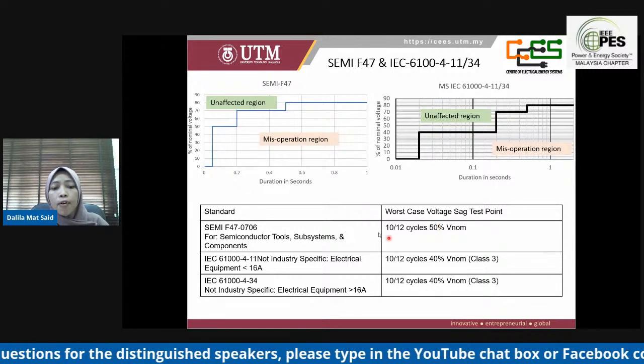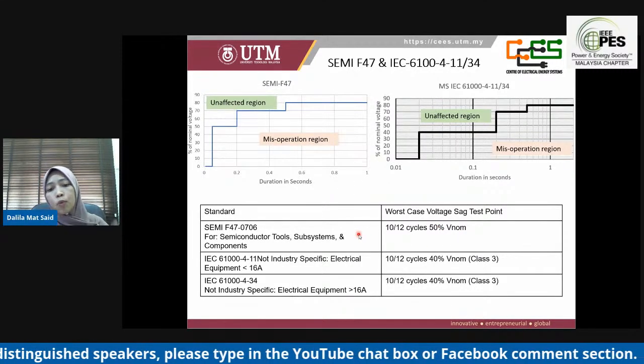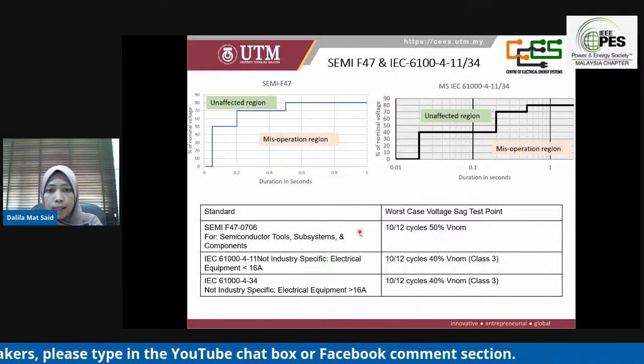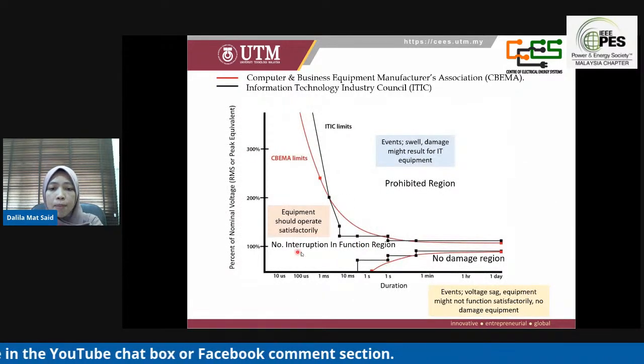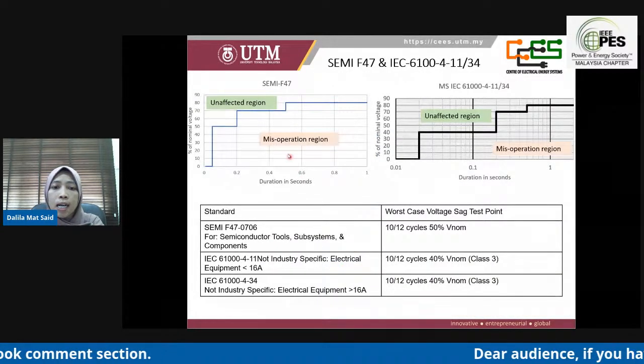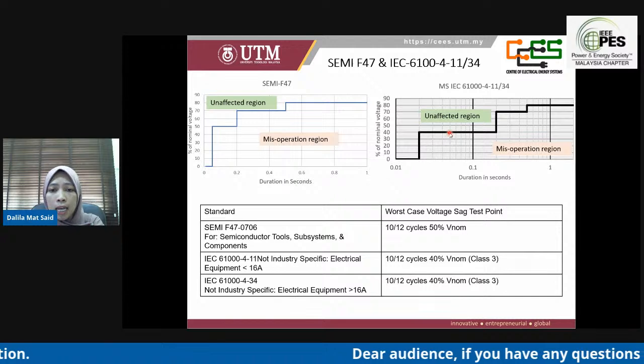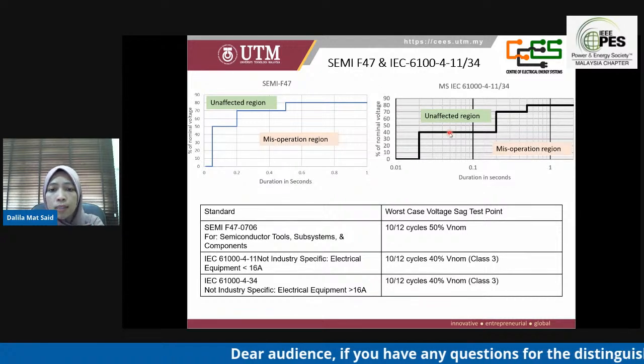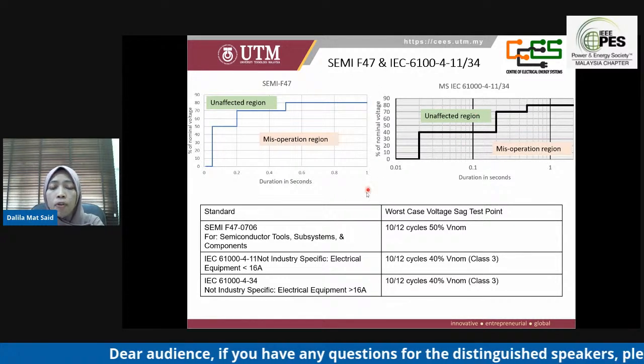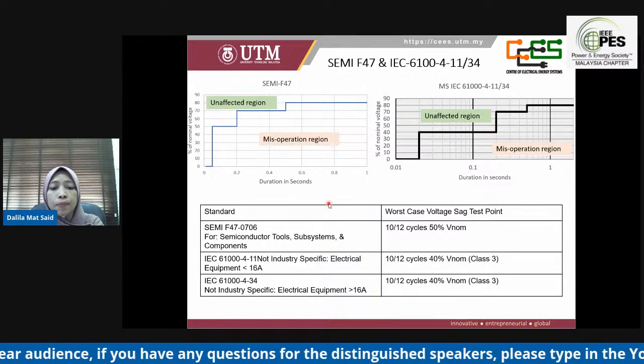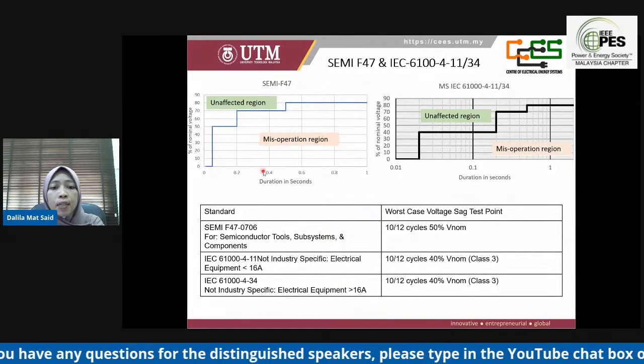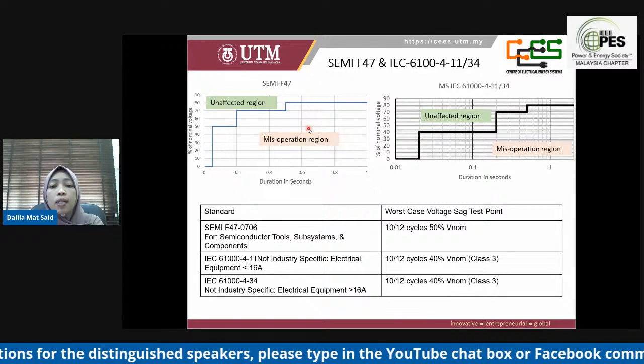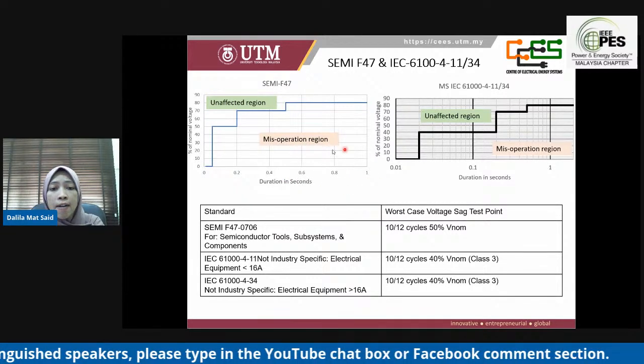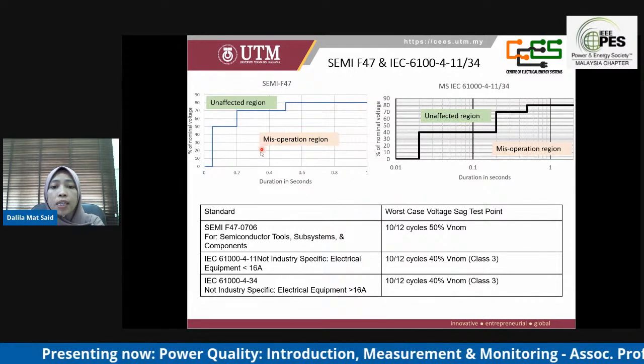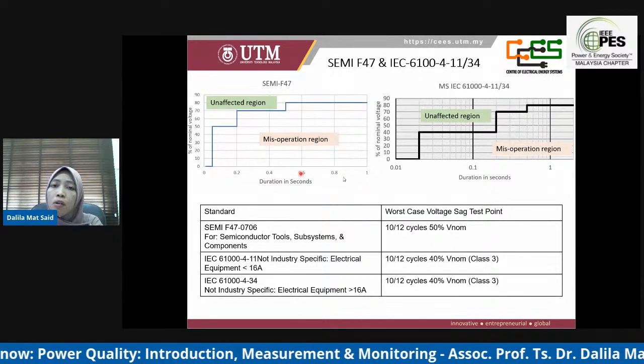Both standards have only two regions. Different from the previous slide, where we saw ITIC and CBEMA have three regions, for SEMI F47 and MS IEC 61000-4-11 or 4-34, we have only two regions, where the region above the curve is the unaffected region and the area below the curve is the misoperation or malfunction region.